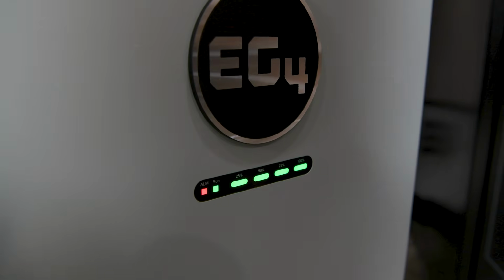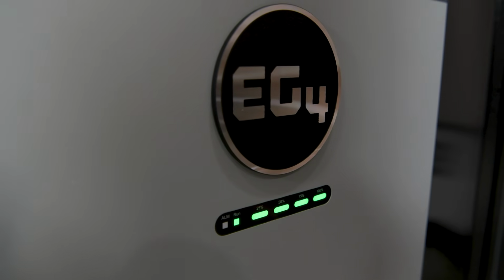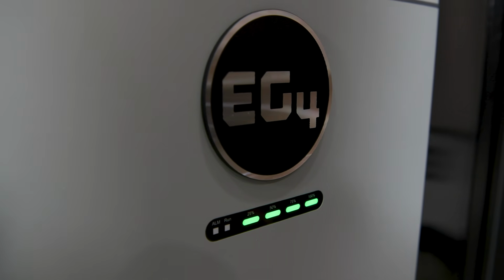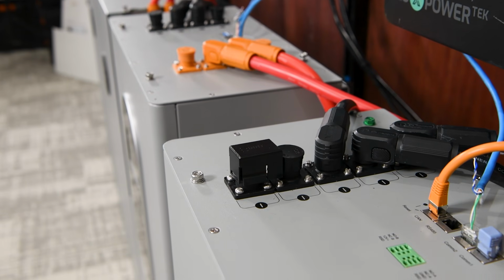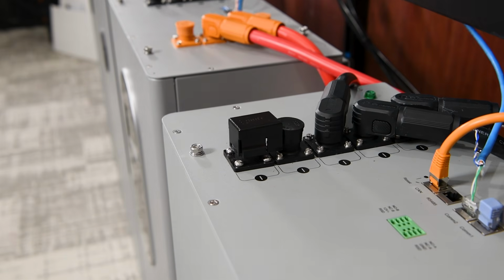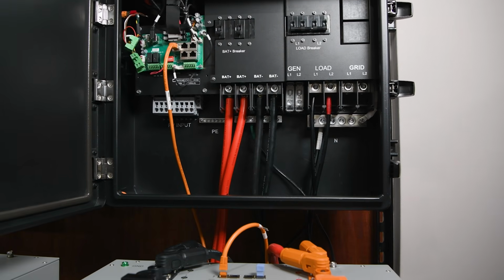After the firmware transfer completes, the battery will restart. During the restart, the LED status lights may flutter briefly. This behavior is normal during the reboot process following a firmware update. If you are running multiple wall mount 314 amp hour batteries in closed loop communication with an EG4 inverter, the system is capable of updating multiple batteries at the same time.